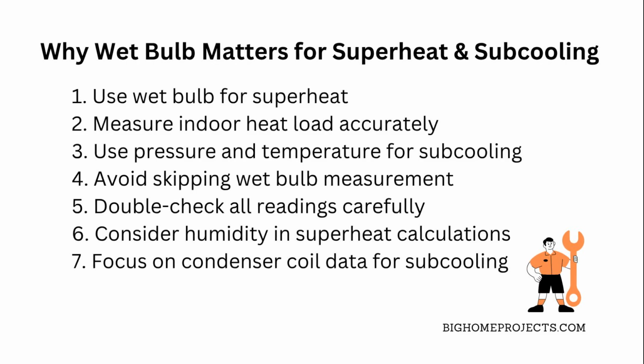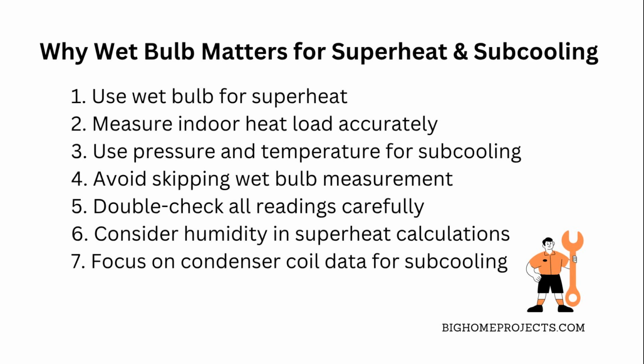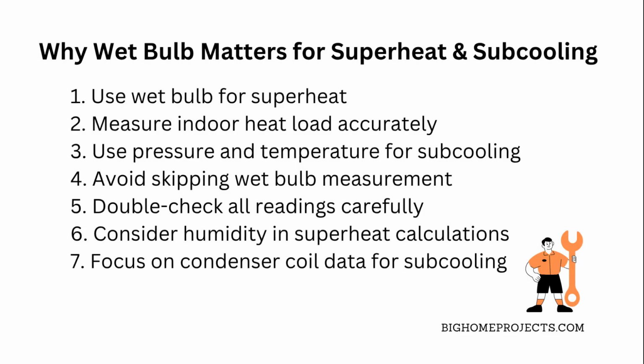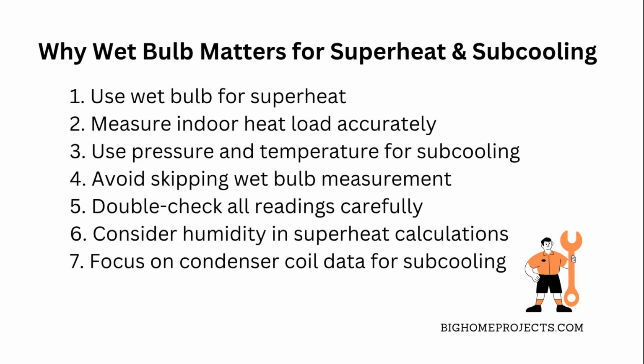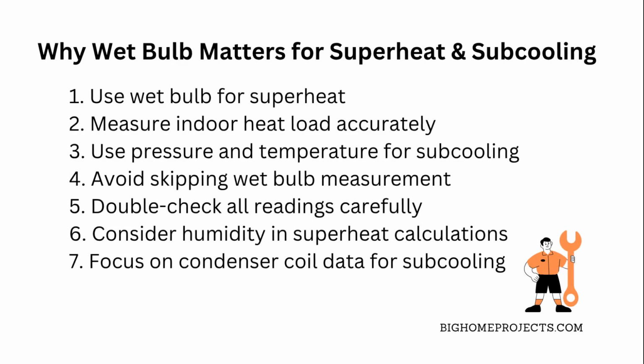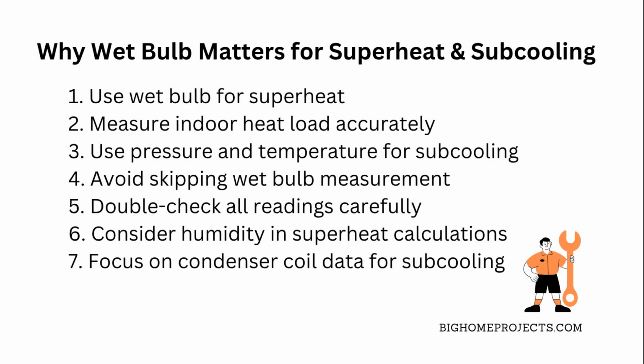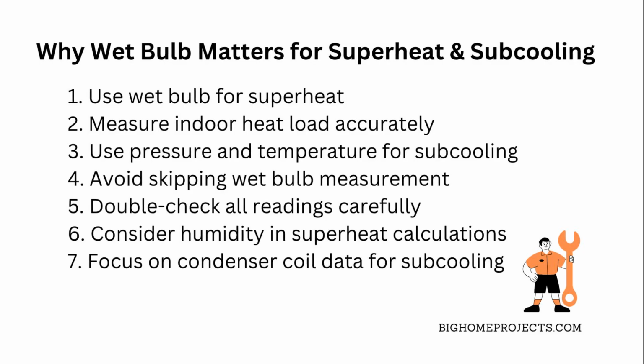Keep your tools handy like a good digital gauge set and an accurate wet bulb thermometer, and always double check your readings to avoid miscalculations. Also, remember environmental factors like humidity when calculating superheat, because wet bulb temp reflects moisture in the air, which impacts heat load. For subcooling, just focus on getting accurate pressure and temperature measurements straight from the condenser coil to see if your system is running too hot or too cold.